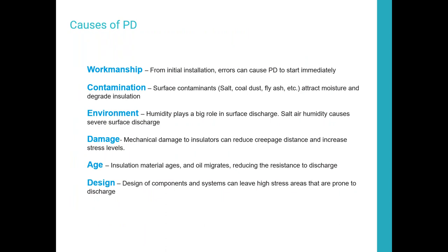Causes: workmanship. We're going to see some examples of workmanship issues, where terminations on cables are not cut back properly and not cleaned properly. The preparation of the termination isn't done properly and will start to immediately cause partial discharge.